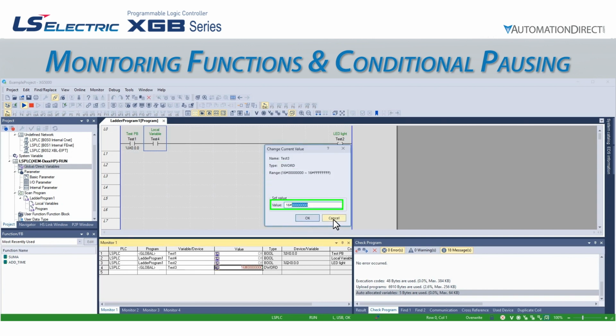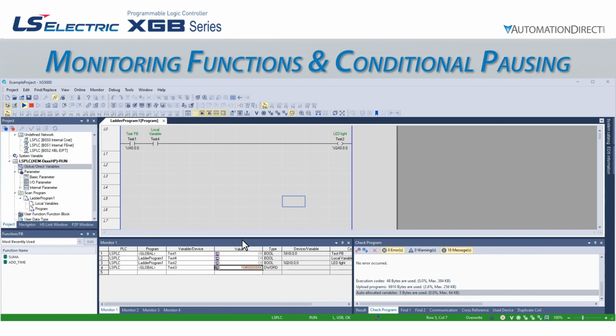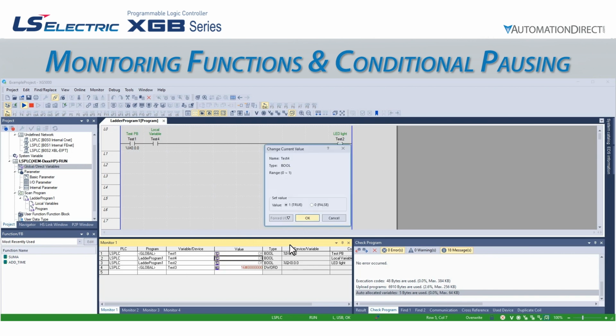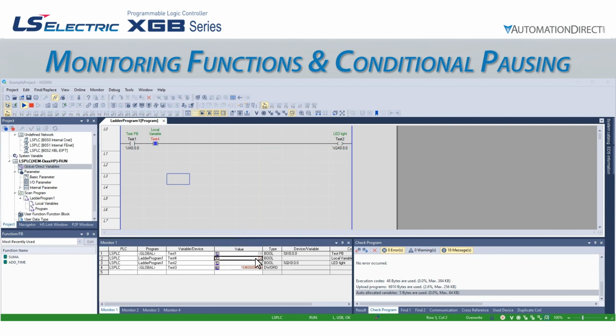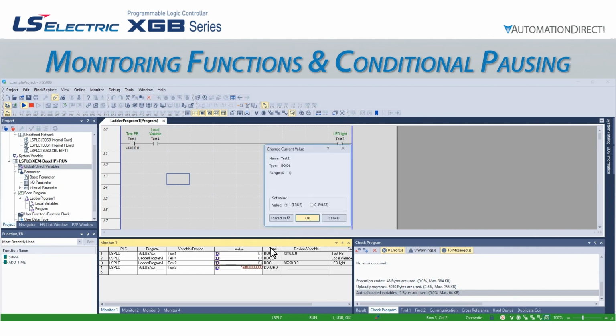If we want to view variables from multiple programs or non-sequential logic, then the easiest and often only way to do this is using the monitor window. We can edit the value of the variable using the value column. If we double-click here, it will open the same Change Current Value screen that we saw when we monitored the variables from the logic. We can set test4 to true, and we see the monitor window change to reflect the new value. Let's do the same thing for test1 and test2.